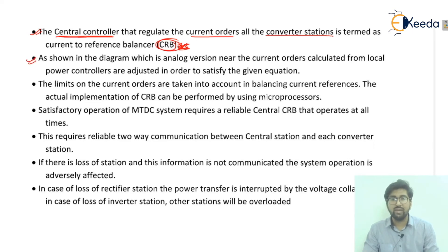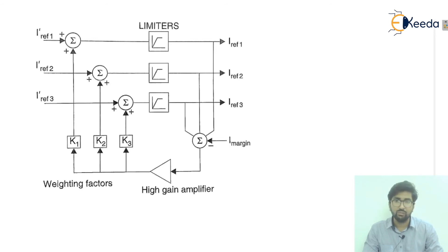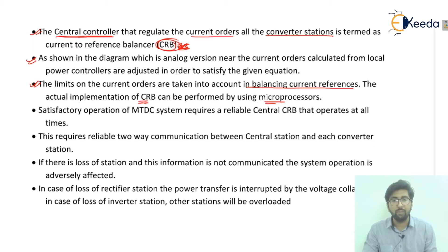The CRB is shown in an analog diagram with limiters, reference currents (I_ref 1, 2, 3), summing points, gains k1, k2, and k3, a high-gain amplifier, weighting factors, and I_margin. The limits on current orders are taken into account in the balancing current reference. The actual implementation of the CRB is performed using a microprocessor.